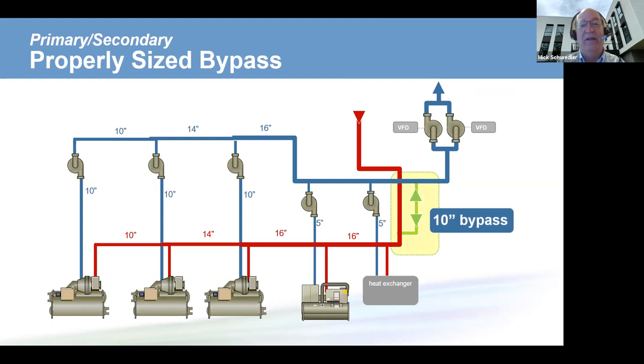And frankly, when I get a chilled water system diagram, which happens multiple times every week, this is the first thing I look for in a primary secondary system. It's easy to find on paper. So it's usually simple to find in the plant as long as we follow where the water is going from where the pumps are. Okay.